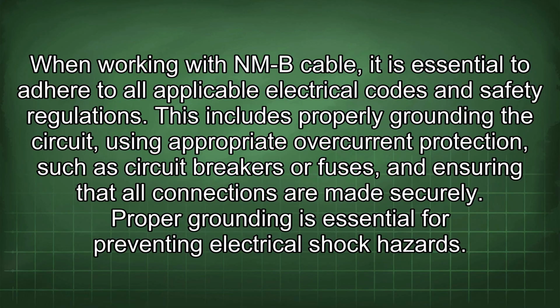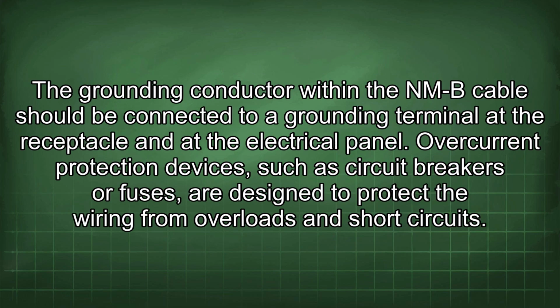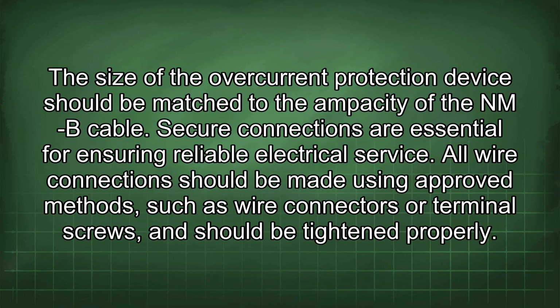When working with NMB cable, it is essential to adhere to all applicable electrical codes and safety regulations. This includes properly grounding the circuit, using appropriate overcurrent protection, such as circuit breakers or fuses, and ensuring that all connections are made securely. Proper grounding is essential for preventing electrical shock hazards. The grounding conductor within the NMB cable should be connected to a grounding terminal at the receptacle and at the electrical panel. Overcurrent protection devices, such as circuit breakers or fuses, are designed to protect the wiring from overloads and short circuits. The size of the overcurrent protection device should be matched to the ampacity of the NMB cable.